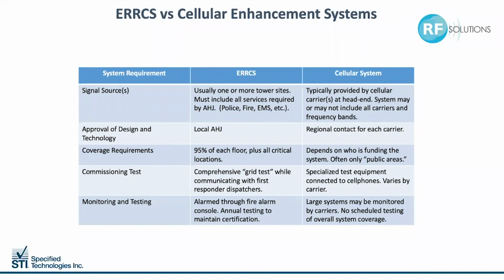ERRCS requires coverage throughout the building, including underground levels, parking garages, and the rooftop. Cellular systems often have a limited area of coverage to keep the price down, or may be installed in a commercial building to serve only one tenant, but not the entire building. ERRCS commissioning tests require coordination with the AHJ and with any local dispatch facilities or 911 centers who originate radio calls to first responders. Cellular testing is carried out using cell phones tethered to data gathering equipment.